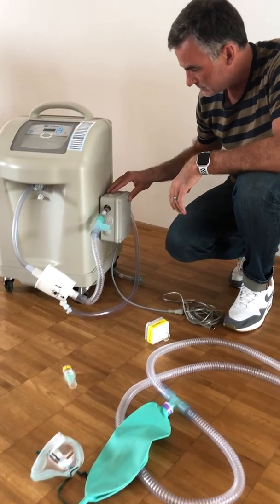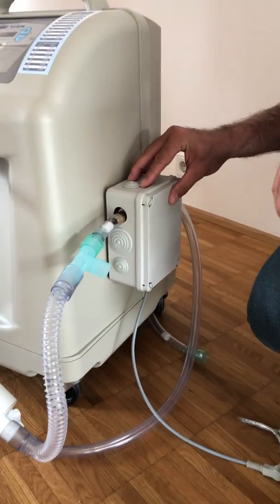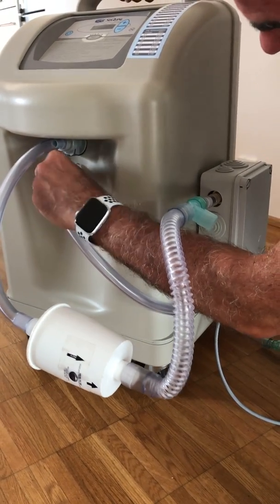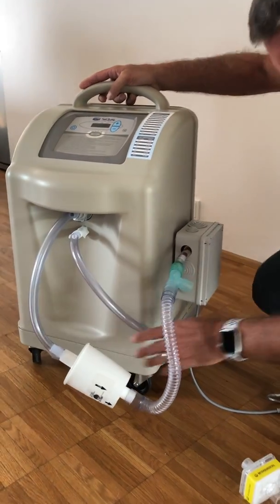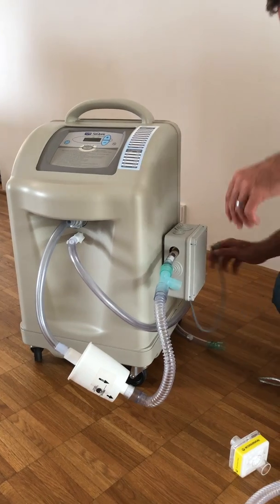The difference to the EHT is that we have the altitude adapter built outside here. So you connect this also to the generator in the front with the small tube, just like this. You can lower it here. And then this cable is to give it electricity from the generator — you place it like here.